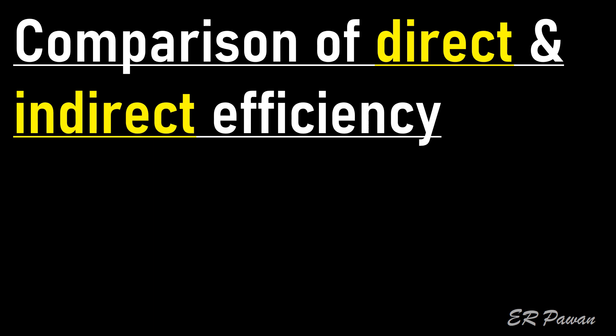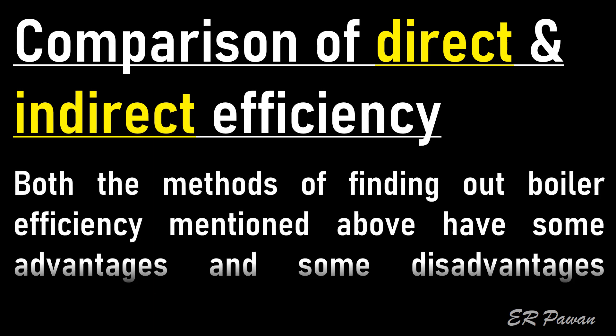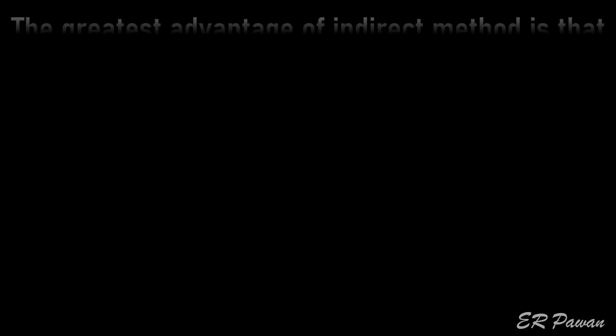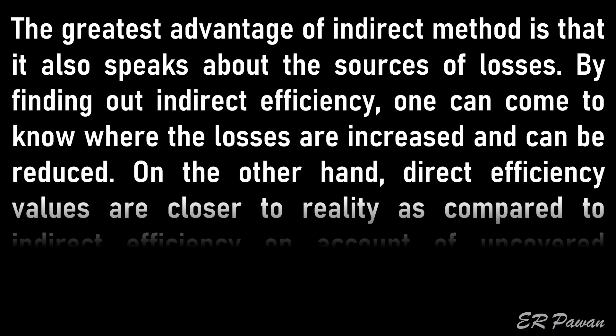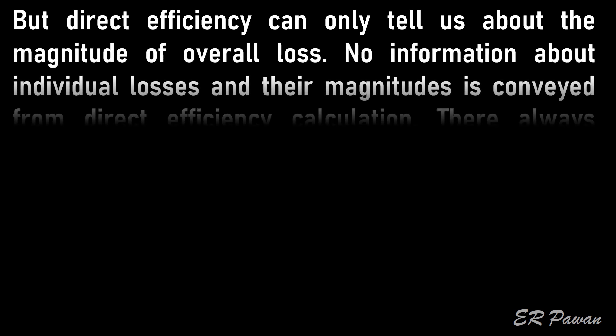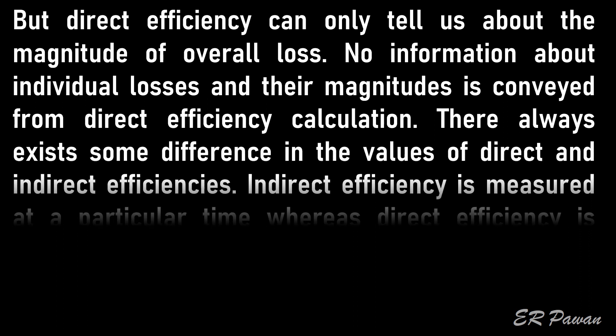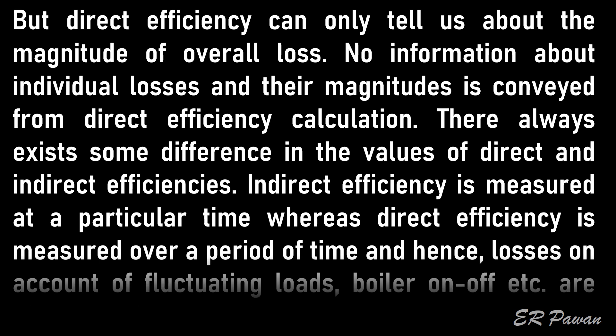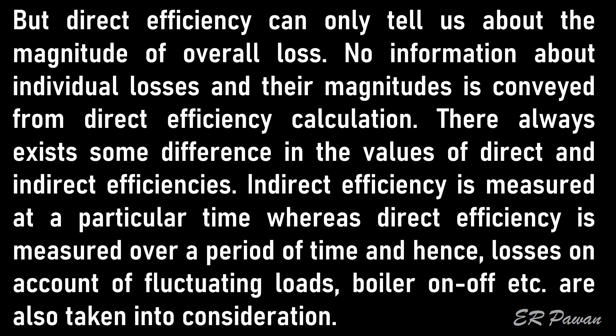Comparison of direct and indirect efficiency: Both methods have some advantages and disadvantages. The greatest advantage of the indirect method is that it identifies the sources of losses, allowing one to know where losses are increased and can be reduced. On the other hand, direct efficiency values are closer to reality, but can only tell us about the magnitude of overall loss — no information about individual losses is conveyed. There always exists some difference between the values of direct and indirect efficiencies. Indirect efficiency is measured at a particular time, whereas direct efficiency is measured over a period of time, so losses due to fluctuating loads and boiler on-off cycles are also taken into consideration.